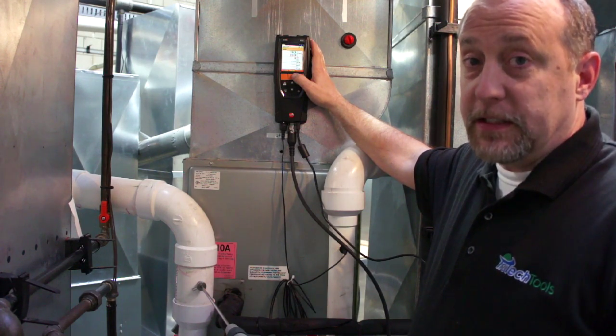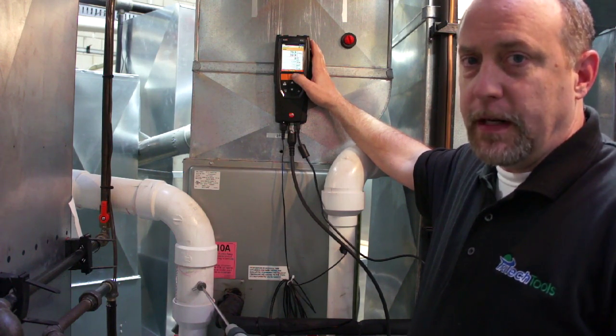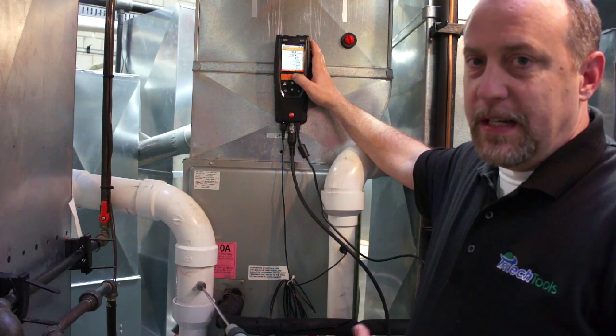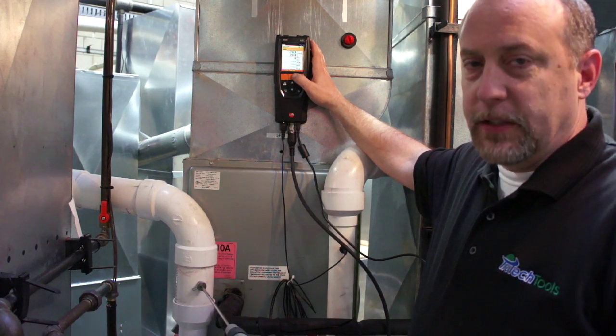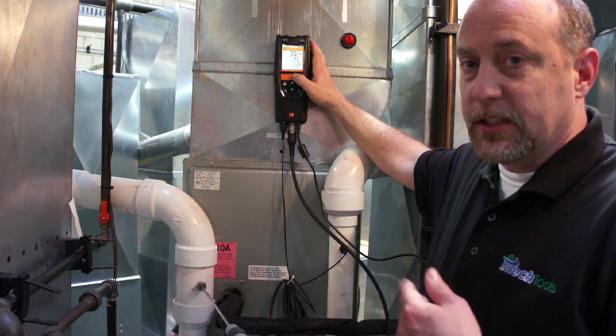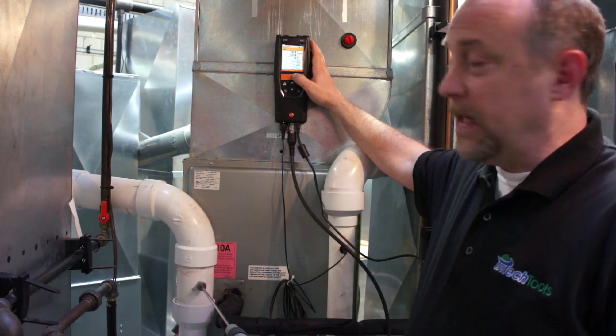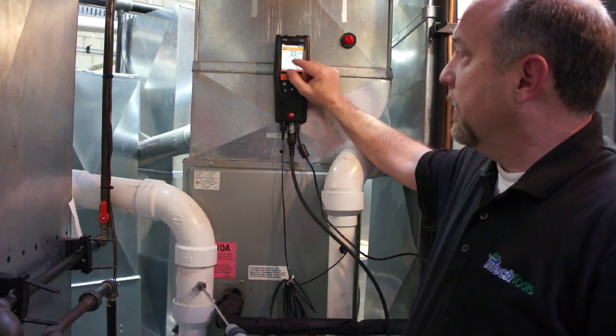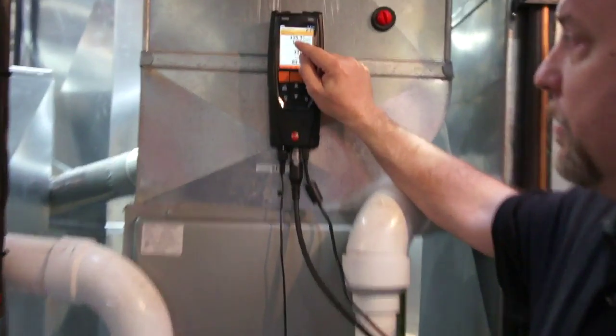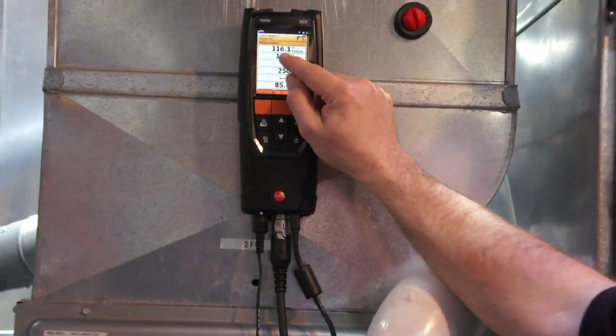We typically expect to see a high CO light-off. That's very common for 90 plus furnaces. There's really no need to expose the analyzer to that high CO reading, so now that it's lit, I'm going to go ahead and start the combustion test. Go ahead and start the analyzer. You'll see right away it's going to register that higher stack temperature because it's in the stack gas.